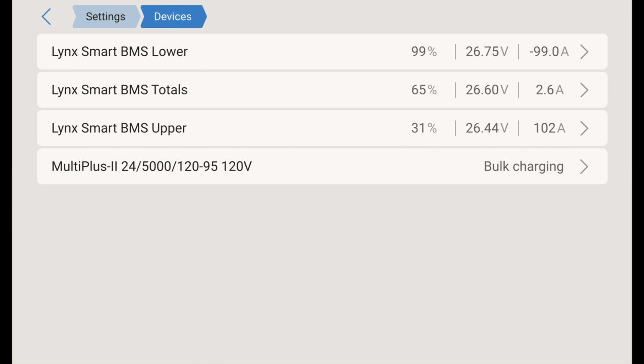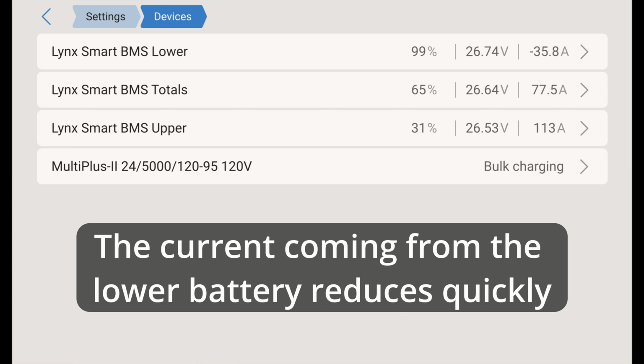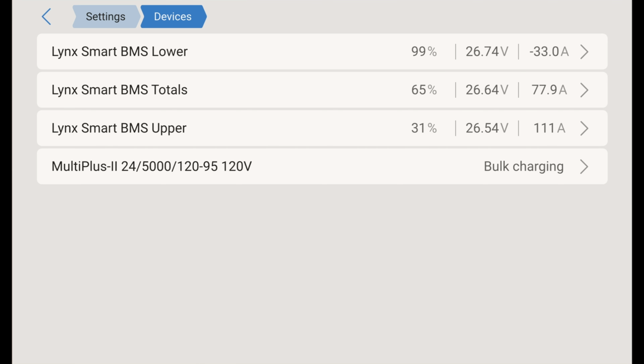It's in circuit. We see a peak of about 118 amps coming out of the lower battery into the upper. That's normal, because it's resting at a higher voltage and it's going to quickly transfer a little bit of its energy. Relatively speaking, that 100 amps is not problematic in any way. And we see that really pretty rapidly drops, already down to only about 35 amps and continuing to reduce as we go.